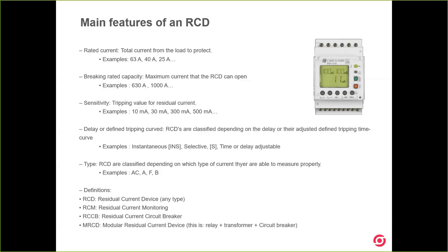You probably know other sensitivities such as 300 milliamps and 500 milliamps. 300 milliamps is very common to protect any kind of loads, and higher values than 300 milliamps are usually used to protect sub-cabinets or main cabinets in the mains of the installation.